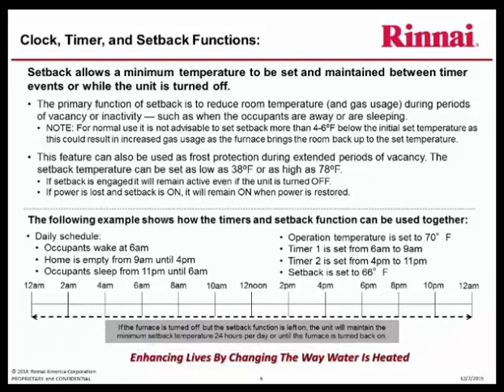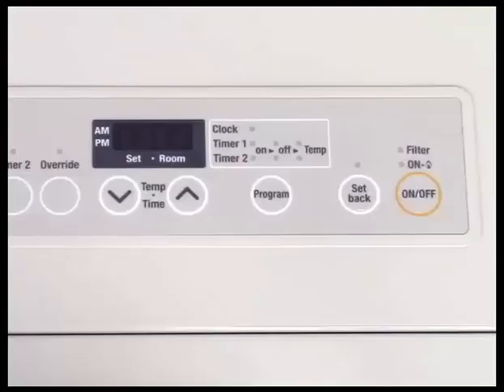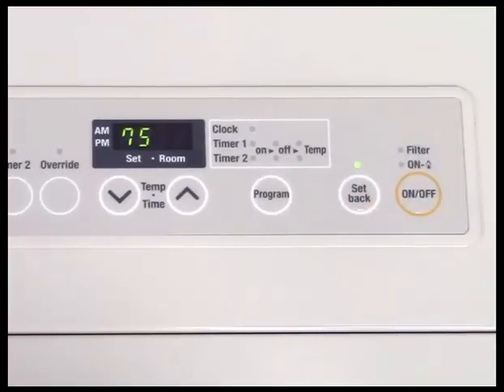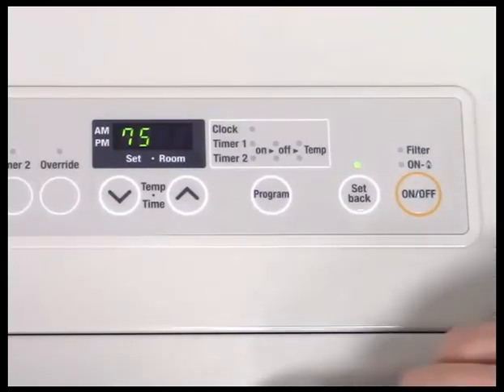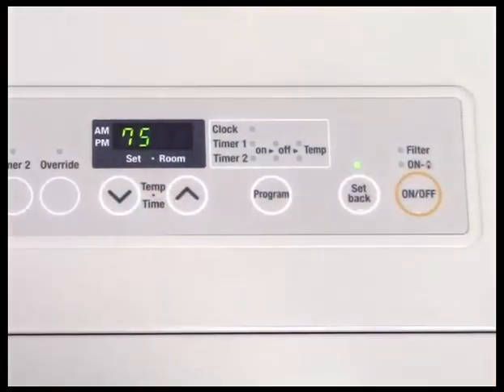If the furnace is turned off but the setback function is left on, the unit will maintain the minimum setback temperature 24 hours a day or until the furnace is turned back on. To engage setback, with the unit turned off but plugged in, press the Setback button. The current setback temperature will be displayed. Use the up or down arrows to change the setback to the desired temperature. Note that when setback is engaged, the unit will turn on and perform a self-test, then turn off if the room is above the setback temperature.